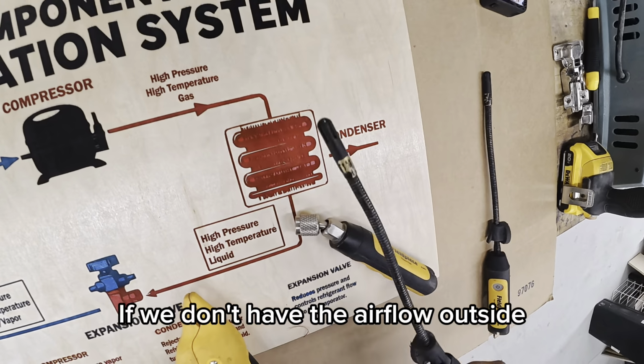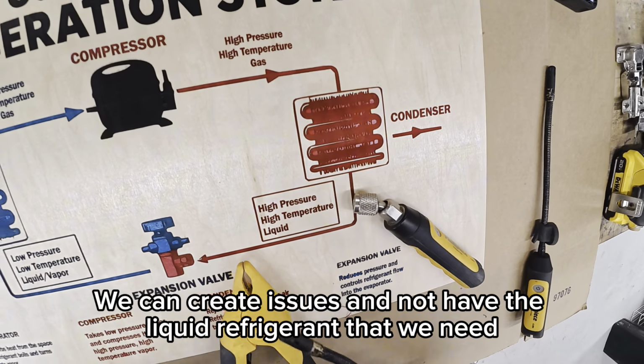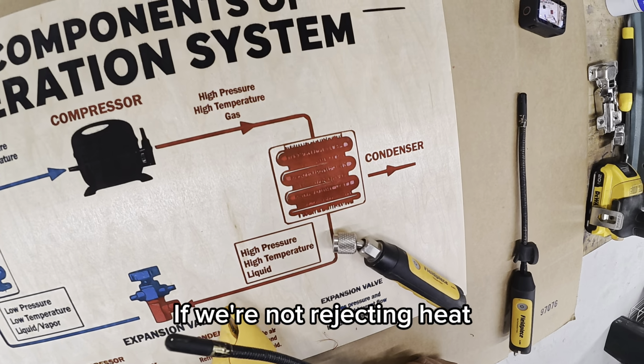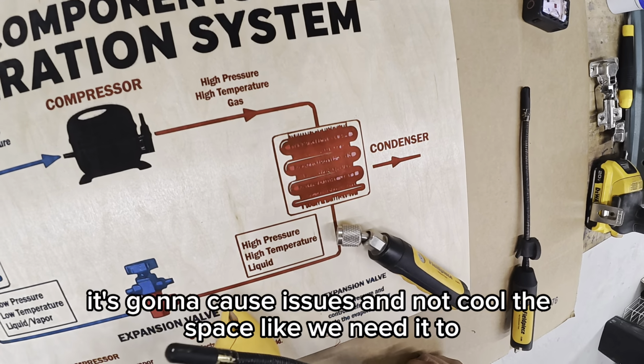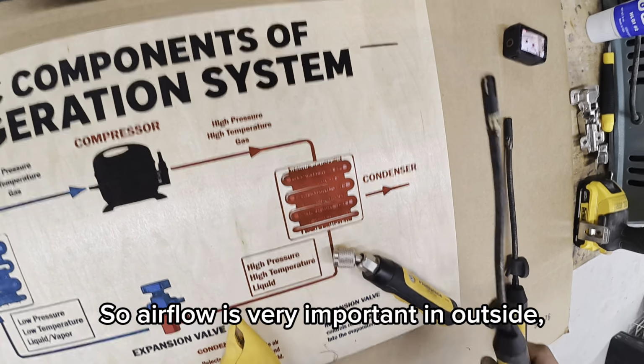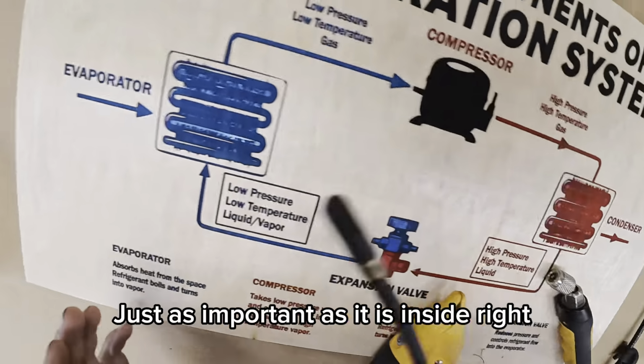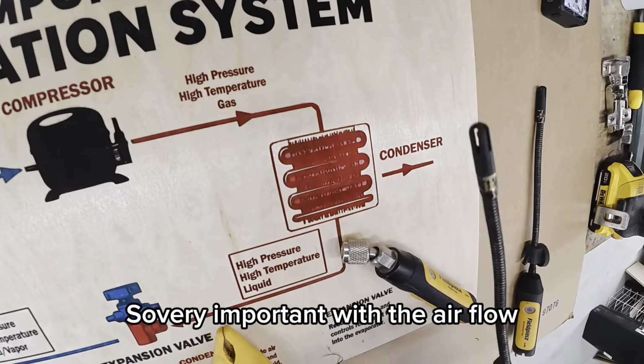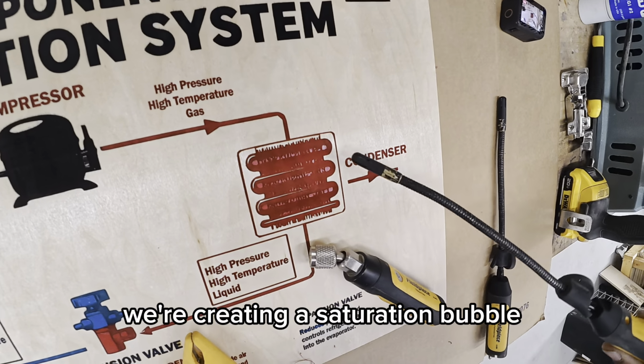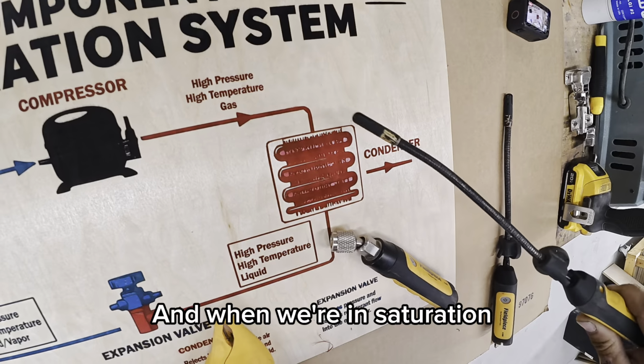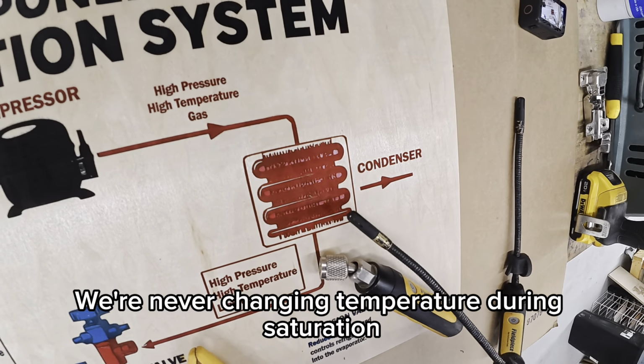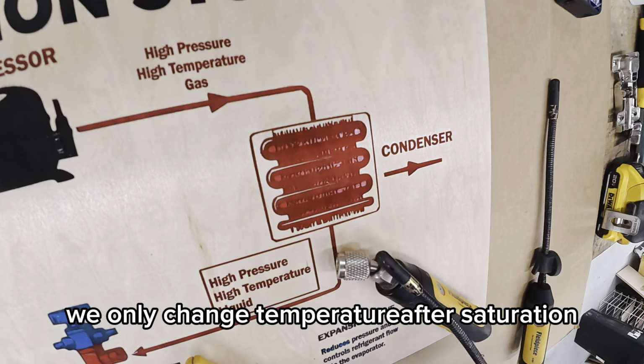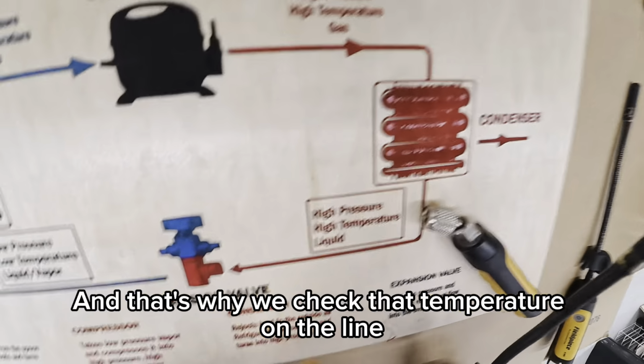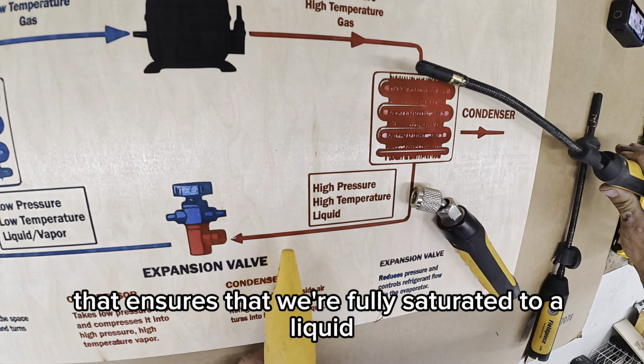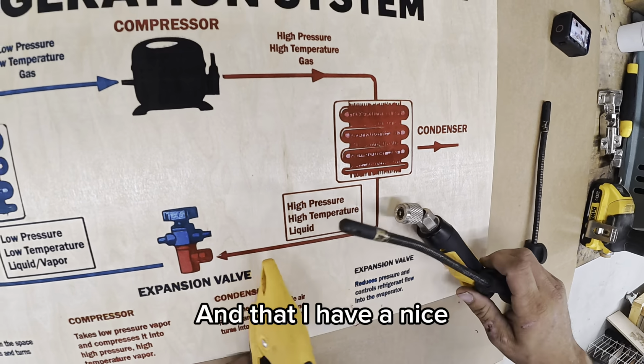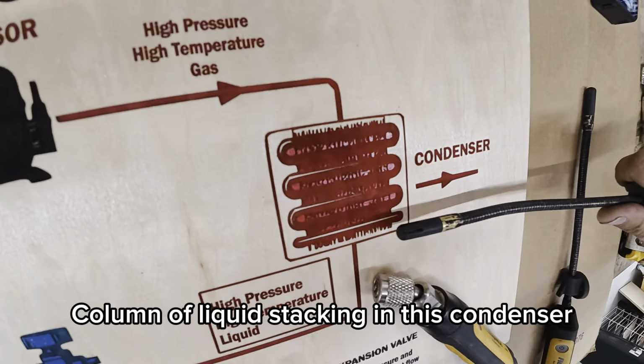If we don't have the airflow outside, we can create issues and not have the liquid refrigerant that we need, right? If we're not rejecting heat, it's going to cause issues and not cool the space like we need it to. So airflow is very important outside, just as important as it is inside, right? So very important with the airflow. But, right, we're creating a saturation bubble. And when we're in saturation, we're never changing temperature during saturation. We only change temperature after saturation. And that's why we check that temperature on the line, that ensures that we're fully saturated to a liquid and that I have a nice column of liquid stacking in this condenser.